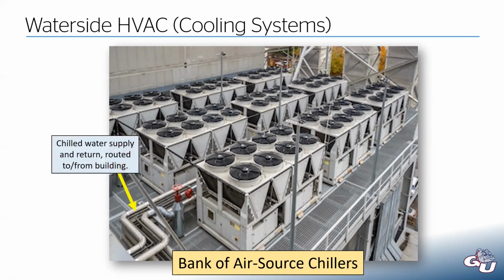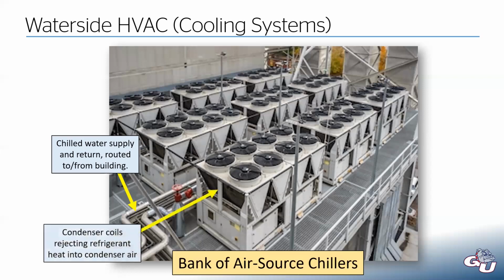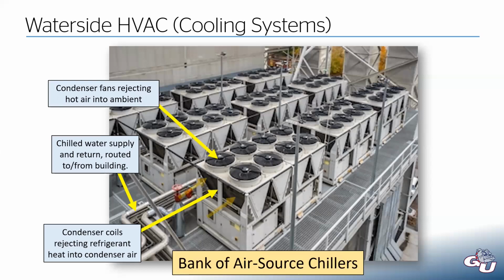So we have our chilled water supply and return. I don't know which one is which, but one is going into the chillers and one is leaving the chillers. We have our condenser coils that are rejecting that refrigerant heat into the condenser air. We have our condenser fans on top, and like I was saying earlier, if you were to put your hand over that fan, it would feel very warm because that's taking in outside air through the side of the coil where we're running our hot refrigerant, and then that air is going to leave warmer. And that's your building heat that we're rejecting outside.